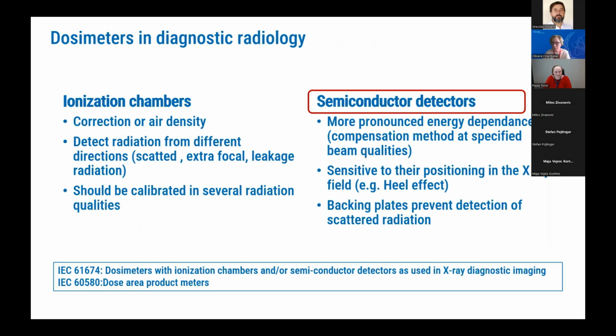Compared to ionizing chambers that are considered to be a gold standard in dosimetry in diagnostic radiology, multimeters are based on semiconductor detectors that have, as already discussed, more pronounced energy dependence that is compensated by different methods introduced by manufacturers. They are also sensitive to the position within the X-ray field, for example, due to the heel effect, and they have backscatter protection, so they are blind to the scatter radiation, which are the facts that differ them compared to the ionizing chambers.